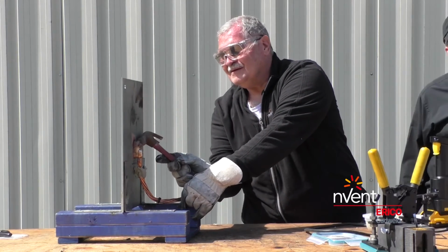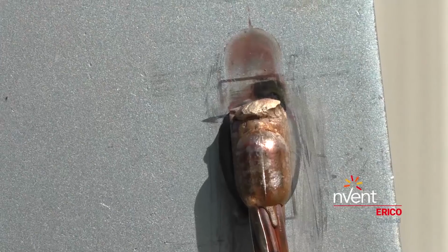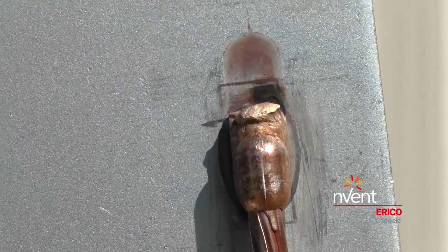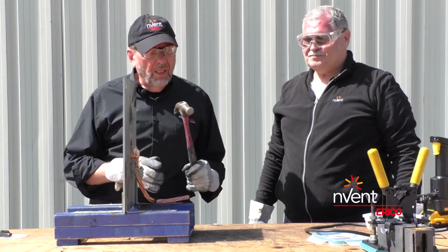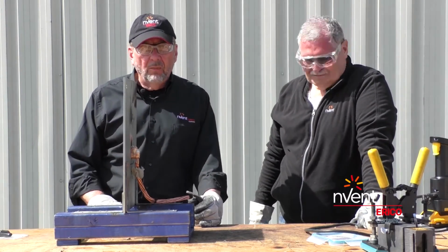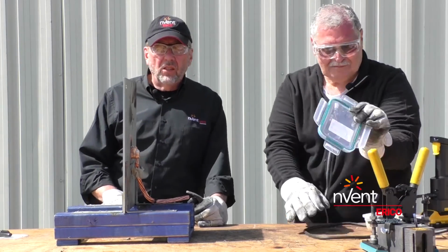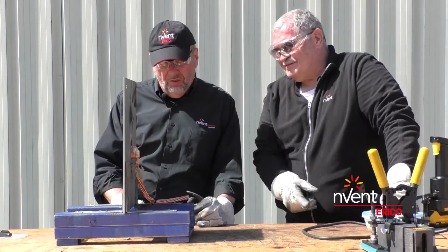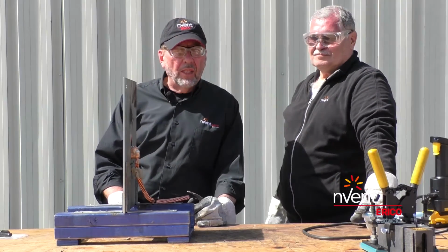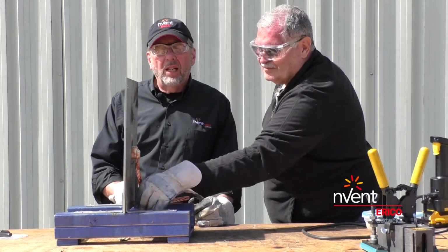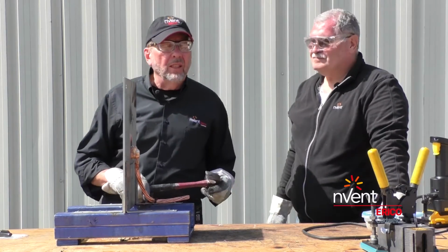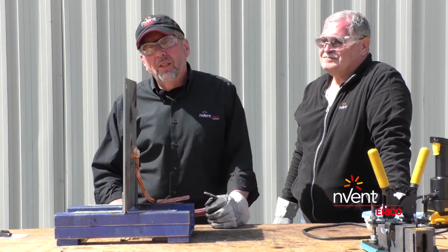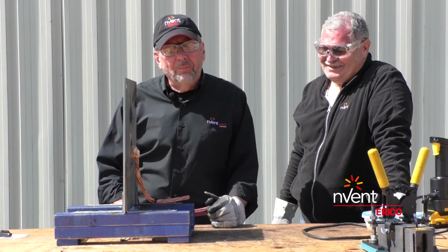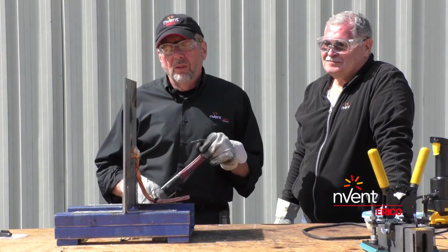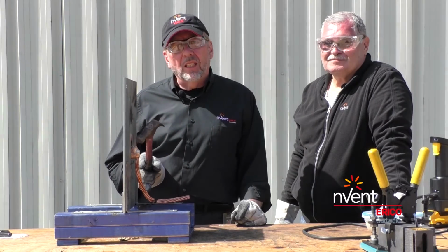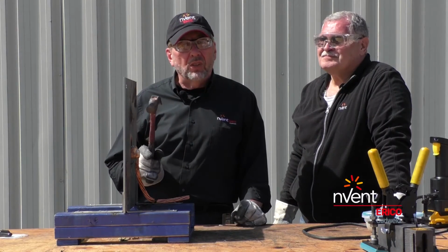So here's another thing folks ask us about very often: testing a Cadweld connection using a hammer. Yes, you can use a hammer to test your finished Cadweld connection, especially something like this, a VB connection to a steel surface. But we don't suggest you find the biggest person on the job site with the biggest hammer they could possibly round up. If you happen to be working somewhere with someone like Thor and his big mighty hammer, we don't want that person to check the weld. We want to use a small hammer, and tap the connection with no more force than I would use to start a nail.